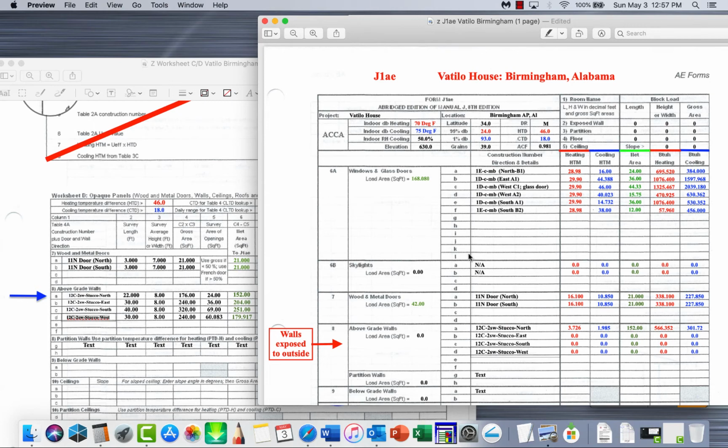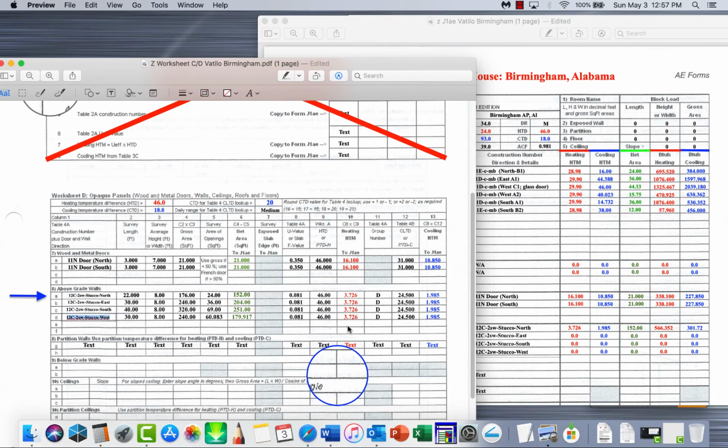Okay. And of course, as we've noticed, our heating here that we're going to transfer back is going right here. So we want to make sure all these are identical, because it's going to be identical. And as you can see, our cooling HTMs are all going to be identical. The only thing that's really going to have a difference is going to be our actual wall surface area, because we got different windows in some walls, we got bigger doors in others. We have a lot of different types of wall space, in other words, like I said. And that's all we're calculating, the total BTUs of that particular material, of wood stud, the R13 blanket and all that. That's all we're calculating, and then we're going to get our BTU load through here.